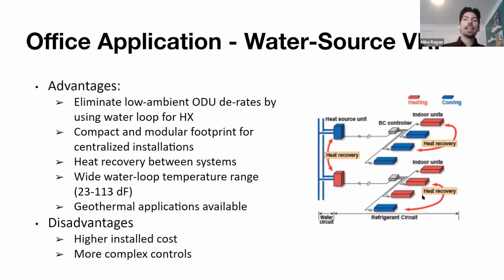So some advantages you could get from a water source VRF is that you don't need to worry about any derates due to ambient conditions. We're rejecting or absorbing heat from a water loop. That's just going to be circulating water. And our systems can operate in a wide range of temperatures, 23 to 113 degrees. So we're not really seeing those substantial derates that some air source equipment may experience. They're incredibly compact. The water source units can actually fit directly into a closet. So if you want to serve water source heat pumps on a per floor basis, that's perfectly fine. You just have this in the water closet where it's just running by this common water loop.